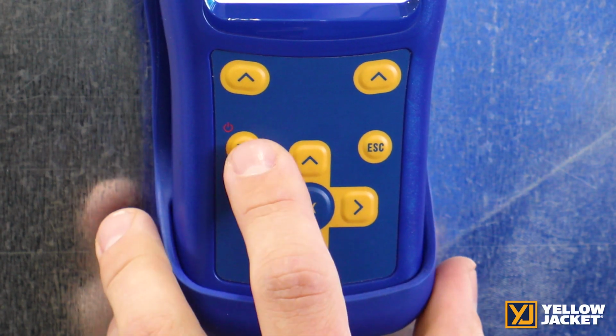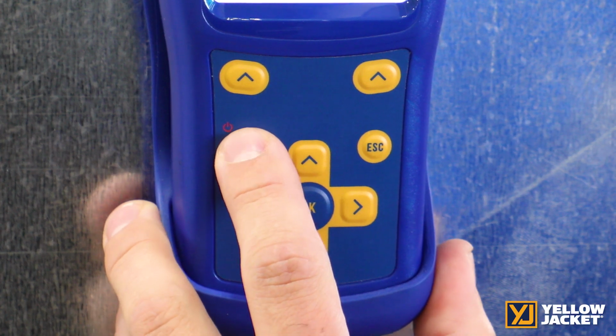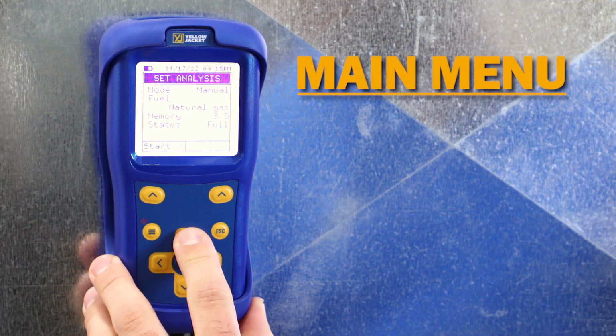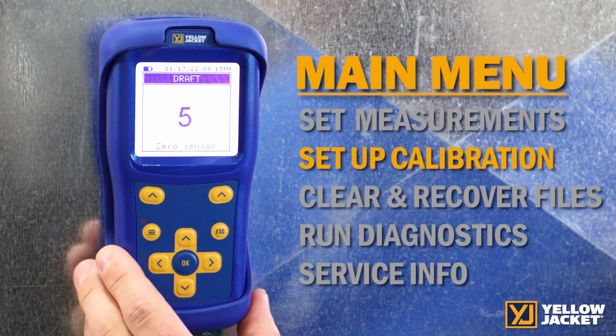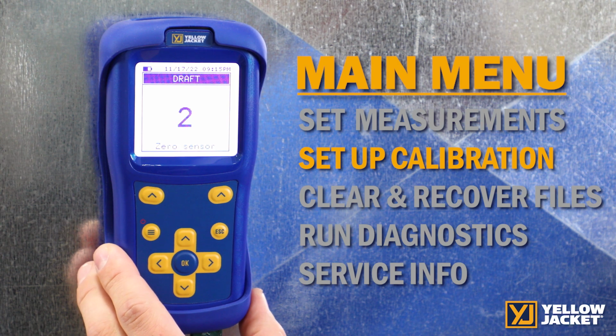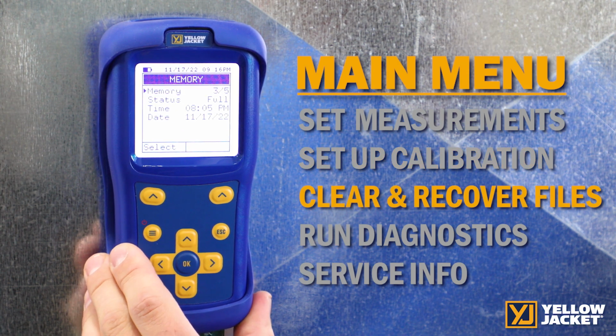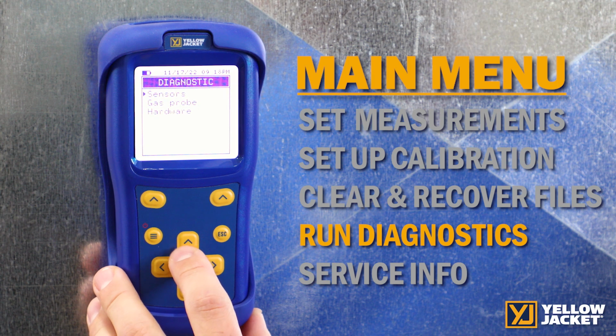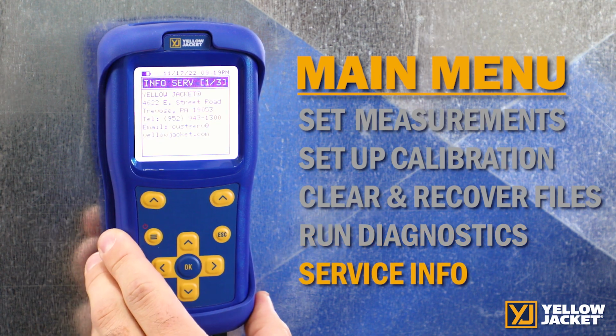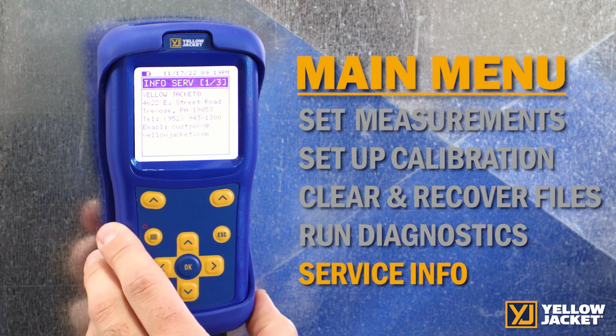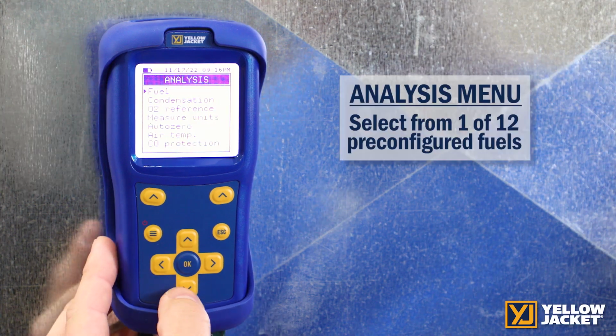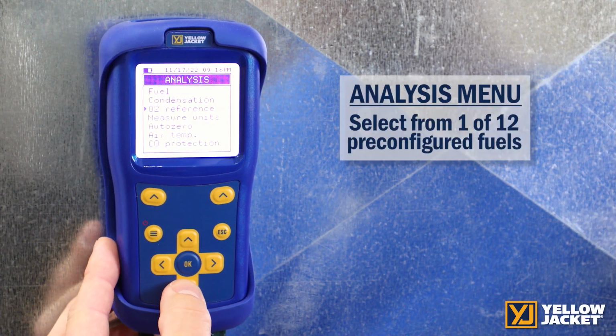Clicking on the power and menu buttons brings up your menu options. This allows you to set measurements, set up your calibration, clear or recover files from the memory, run diagnostics, and it will even show you where you can send in your analyzer for service. In the analysis menu, you may select from one of 12 pre-configured fuels.